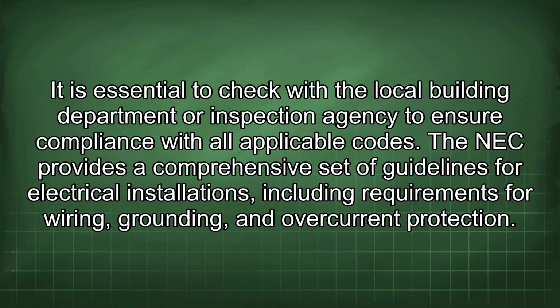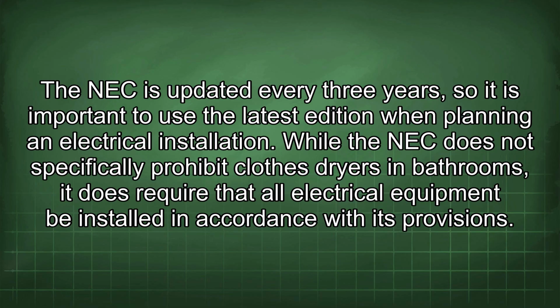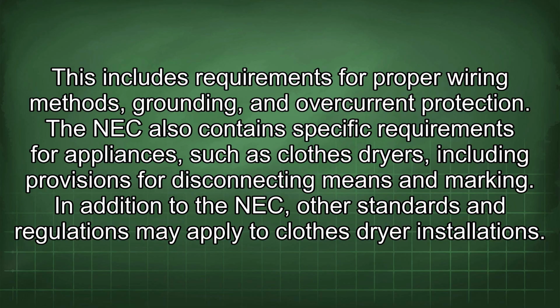The NEC provides a comprehensive set of guidelines for electrical installations, including requirements for wiring, grounding, and overcurrent protection. The NEC is updated every 3 years, so it is important to use the latest edition when planning an electrical installation. While the NEC does not specifically prohibit clothes dryers in bathrooms, it does require that all electrical equipment be installed in accordance with its provisions. This includes requirements for proper wiring methods, grounding, and overcurrent protection. The NEC also contains specific requirements for appliances, such as clothes dryers, including provisions for disconnecting means and marking.